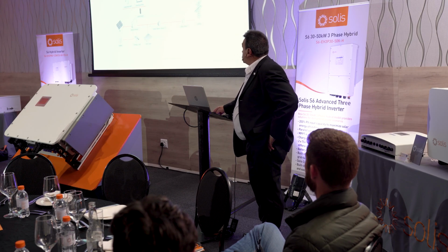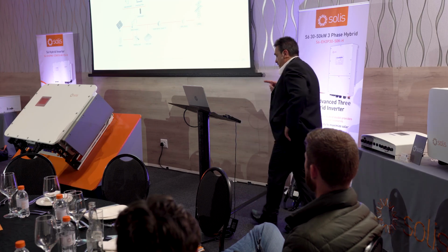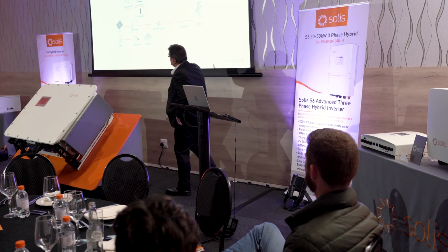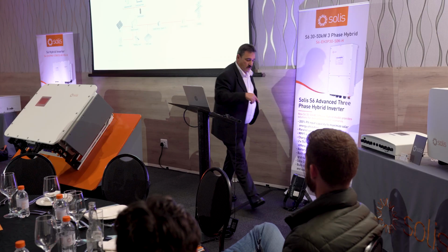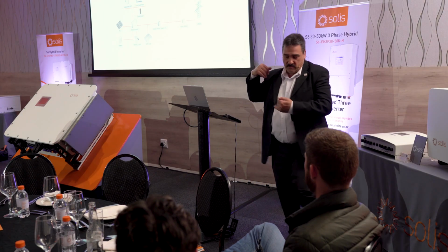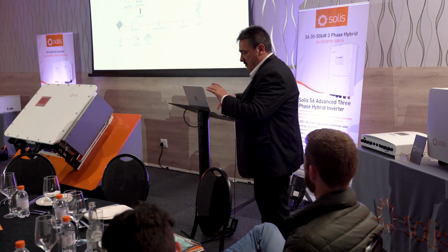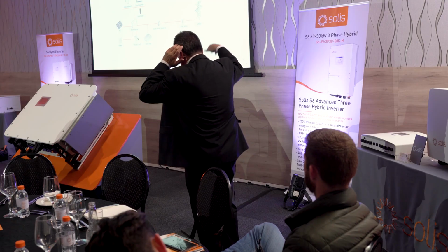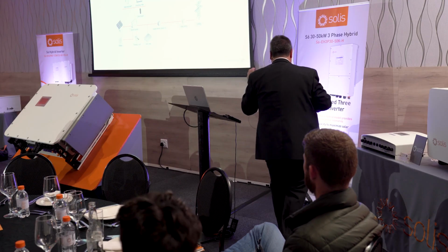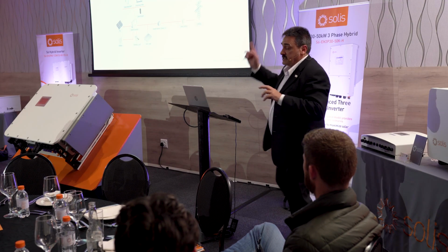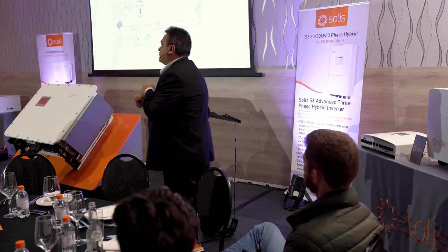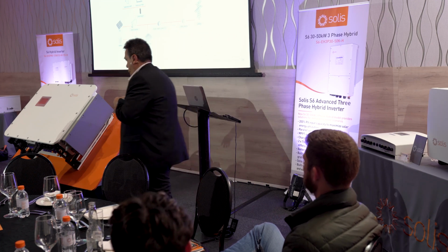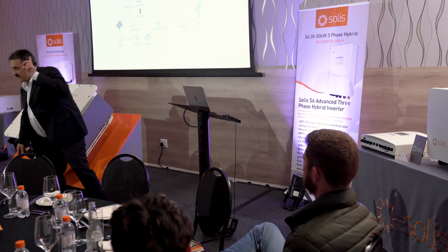Okay, so you also have the option, and in this mode, like setting first, you can set the priority. If we just go back to the previous one, let's look at the mode priorities. I think there's a slide later on that comes with it, but we can skip over that one. So the priority in self-use mode is that the load takes first priority, right? The backup load comes out here. That is the first priority, always.